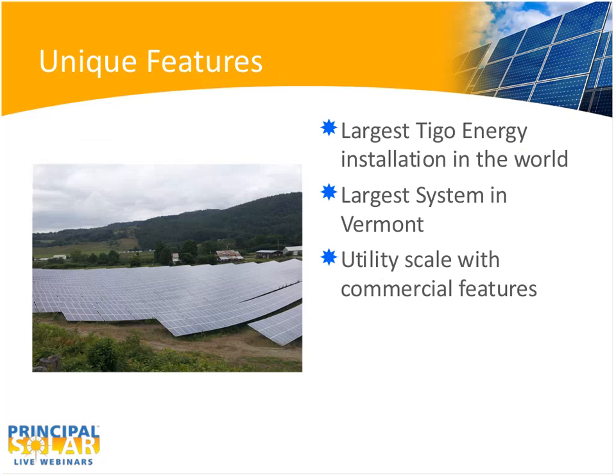The Tigo energy component was the add-on that potentially could have separated us from the other 2.2 megawatt projects in Vermont. Their increased performance, although untested at this scale, was enough of a potential gain for us to take a serious look and actually take a risk installing them. We ended up only installing Tigo on 90% of the panels, with 10% installed without the maximizers, so we'll have the opportunity to compare performance at the same site, with the same inverters and the same weather conditions. It'll be a fair experiment, and we'll see if there's actually an increase in performance.